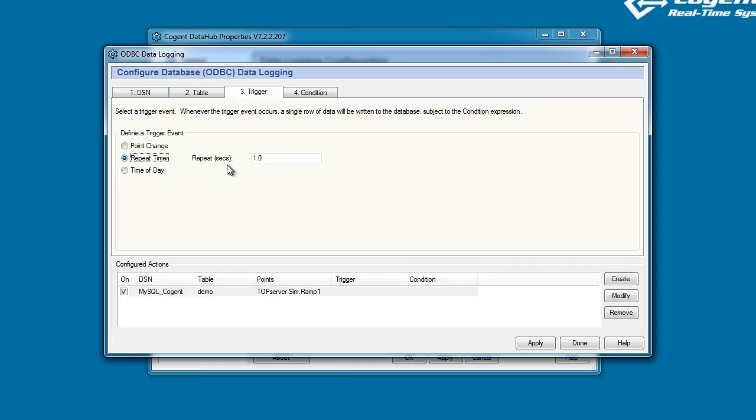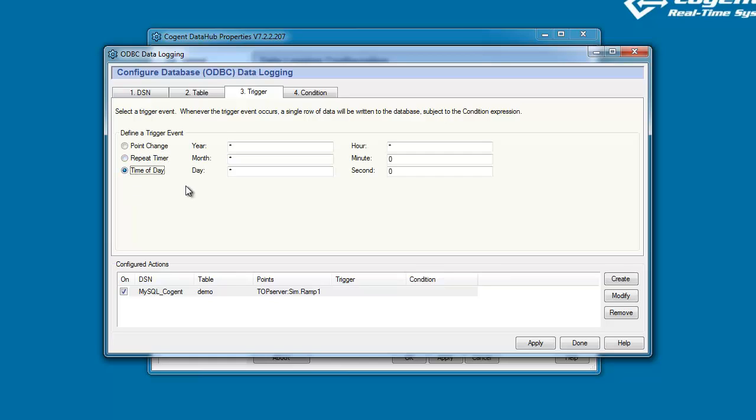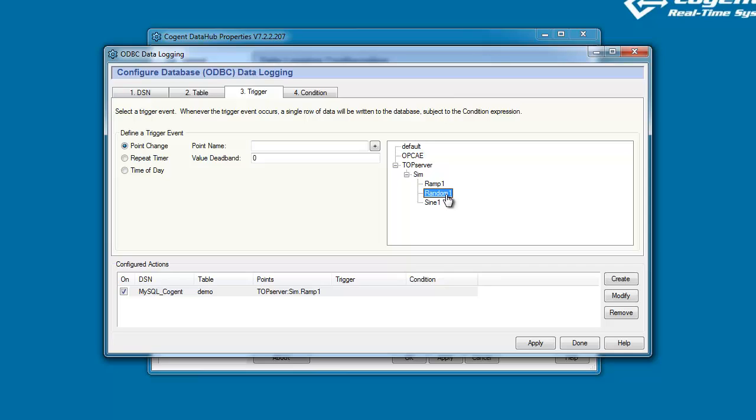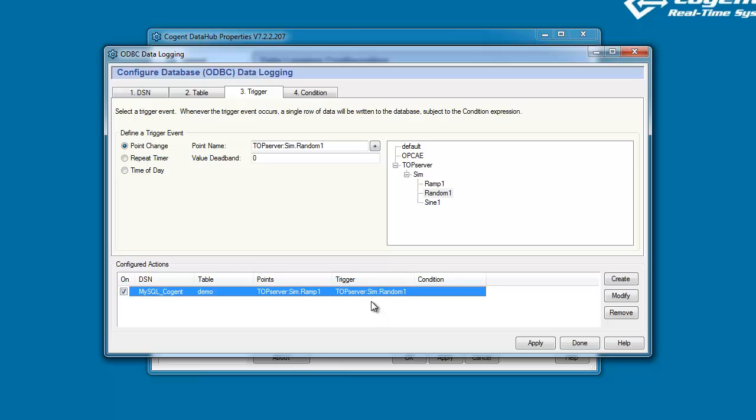A repeat timer, so for example we can trigger the event every five seconds. Or a time of day, so we could say every day at midnight we want to trigger our configured action. For this video, I'm going to come back and choose a point value. And I could choose the value for Ramp1, the point we want to log to the database, but you don't have to, so in this case I'm going to trigger from a different point, this one being the Random1 point. So now I will click on Modify, and that adds our trigger point.